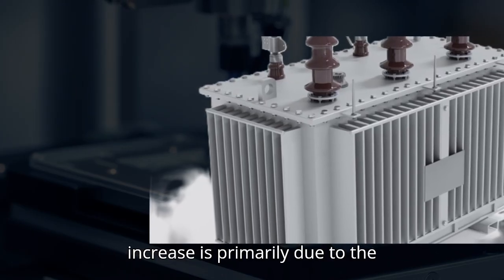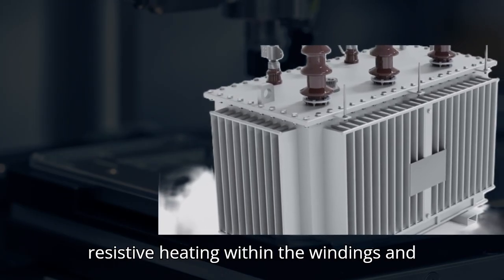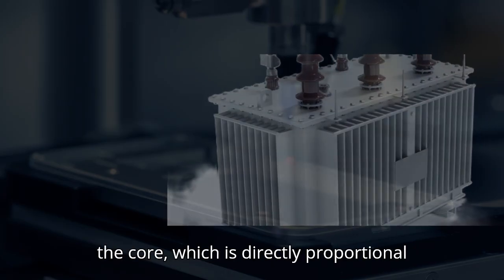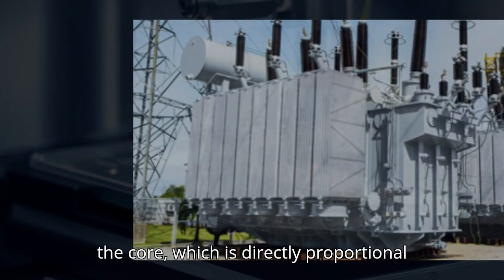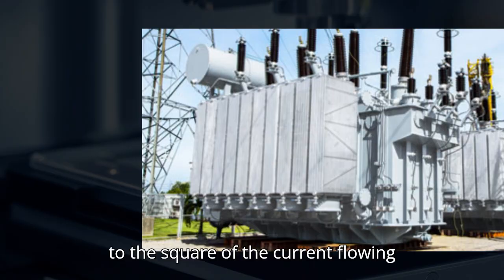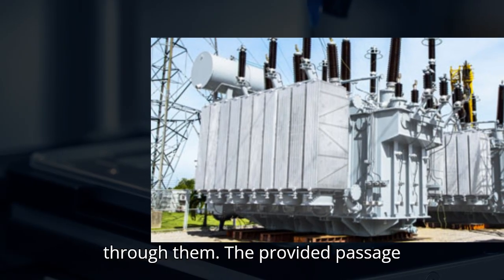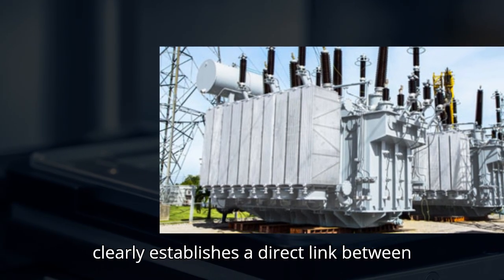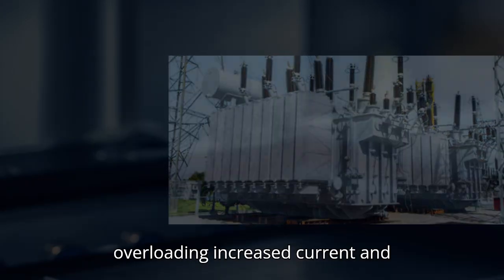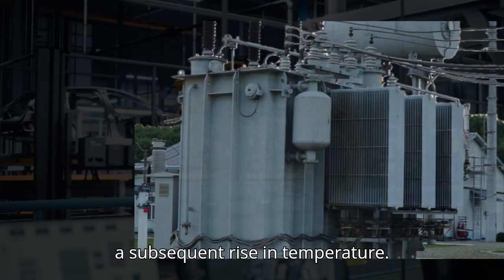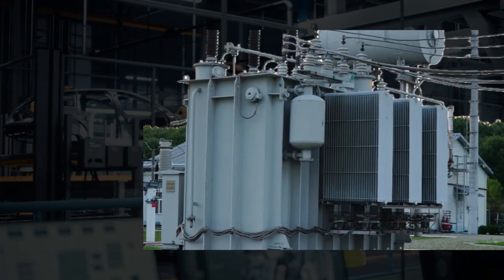This temperature increase is primarily due to the resistive heating within the windings and the core, which is directly proportional to the square of the current flowing through them. This clearly establishes a direct link between overloading, increased current, and a subsequent rise in temperature.